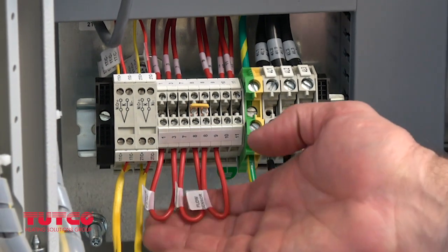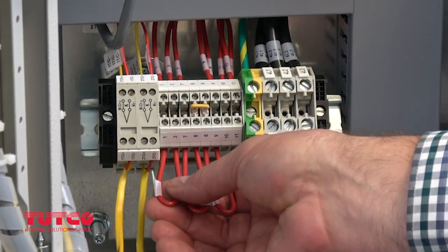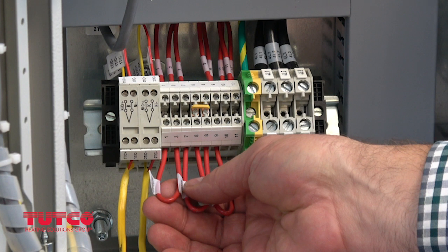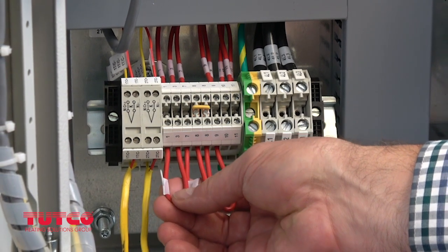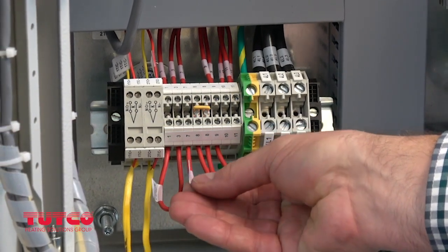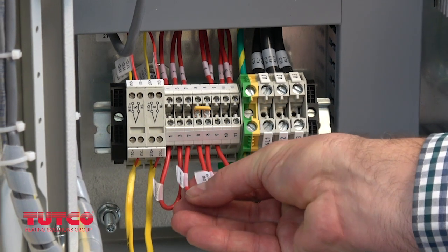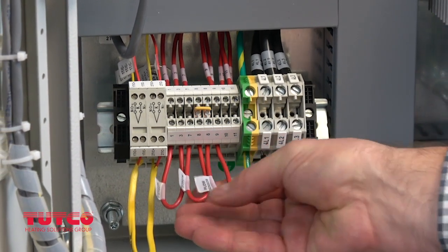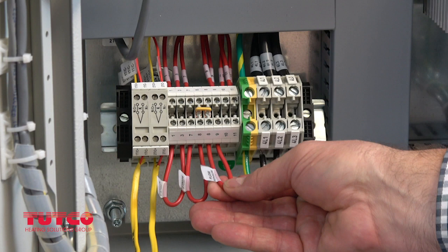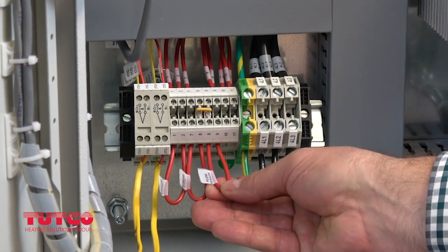Look at the terminal blocks. There is a remote e-stop across terminals 1 and 3. Terminals 7, 8 are for the remote stop command. Terminals 8 and 9 are for the flow sensor or any other device used to stop the heater from working due to an unwanted condition. Terminals 10 and 11 are not used at this time.